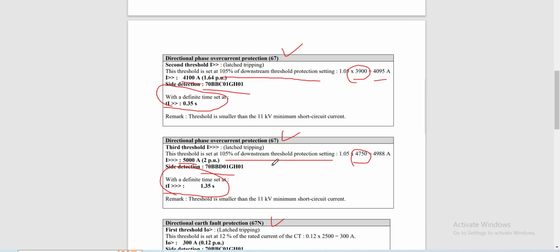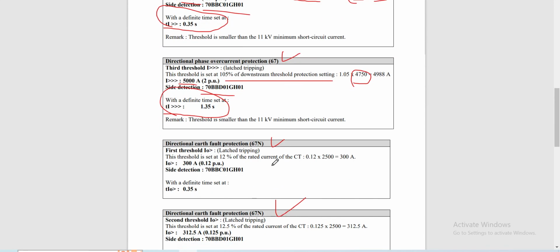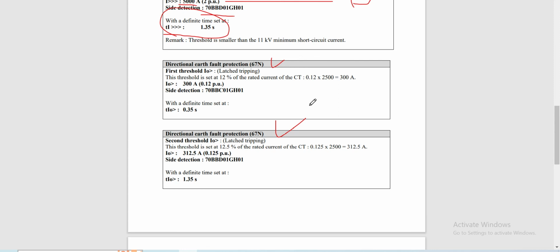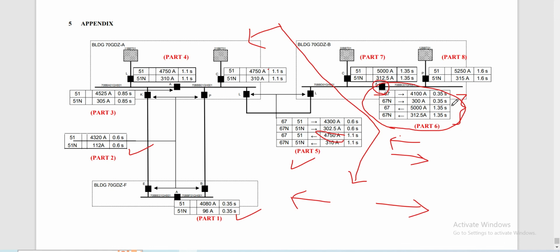So, for the review of the overcurrent protection, we have 3 thresholds. For the first threshold, we use the time overcurrent protection. For our second and third thresholds, we use directional phase overcurrent protection. For our earth fault protection, we are going to use directional earth fault protection. Remember we have 2 thresholds here: going to the right at 0.35 seconds and going to the left at 1.35 seconds.